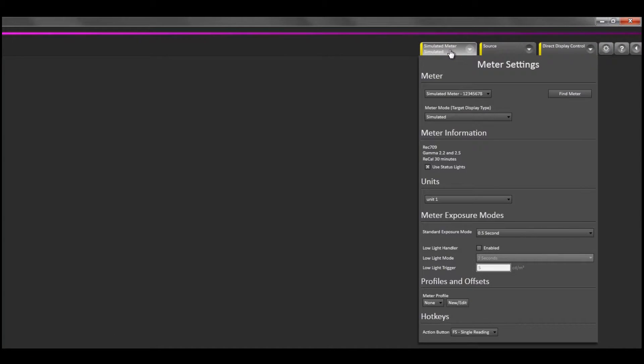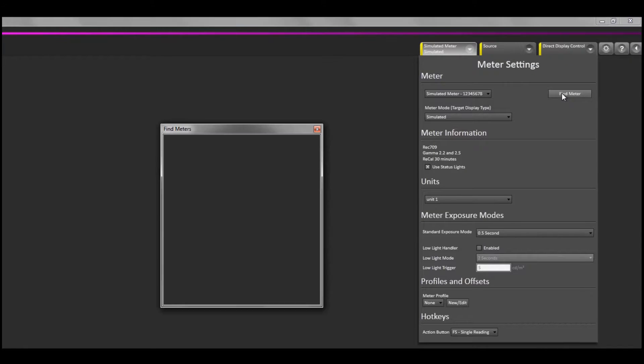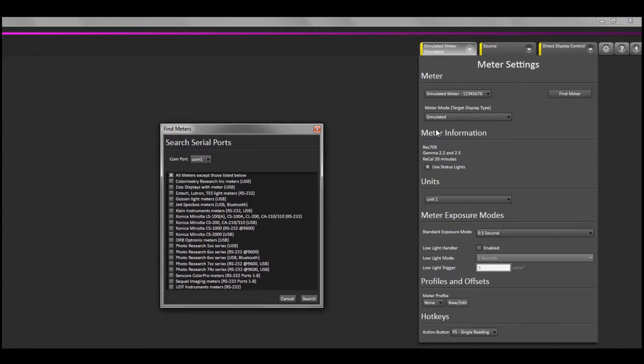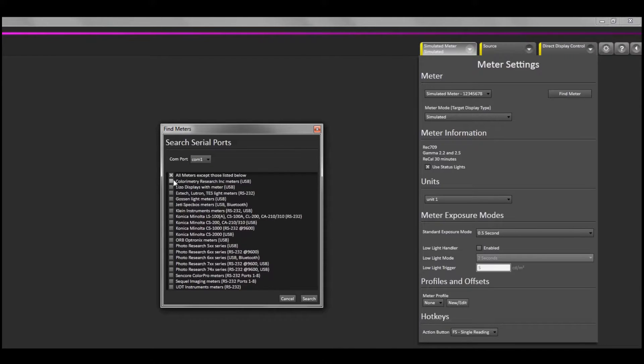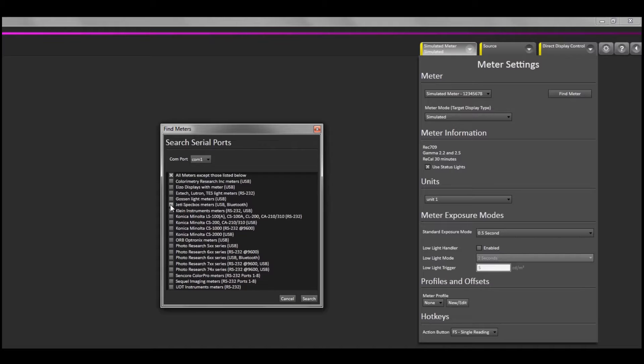Once CalMAN is open, I will go to the Meter dropdown tab to find the meter. I will click Find Meter, and from the pop-up window, I will go ahead and do a search for the meter. Please note that there are some specific meter types here that require you to actively select the device you're trying to connect to.